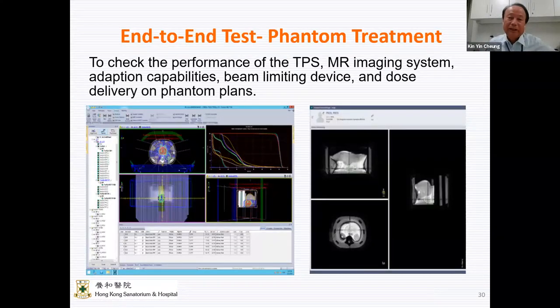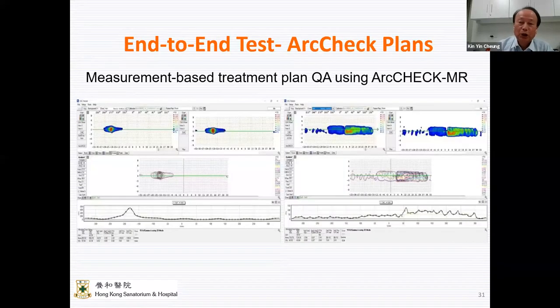Now, after that, we do an end-to-end phantom treatment delivery from MR scan, and then do a bit of adaptation planning, and then deliver the treatment as though the phantom is a patient. And then we can transfer this plan, just like a patient plan, to a Sun Nuclear ArcCheck system, do an ArcCheck plan irradiation, and then measure the dose and also the gamma analysis to see if they agree with the treatment plan.